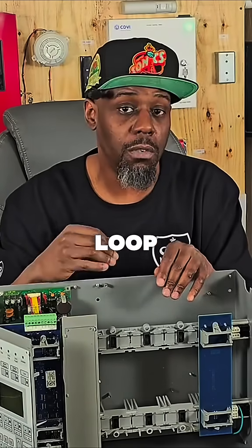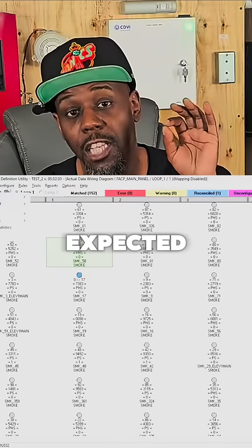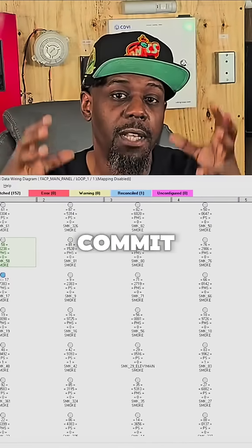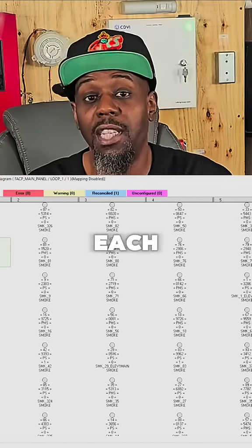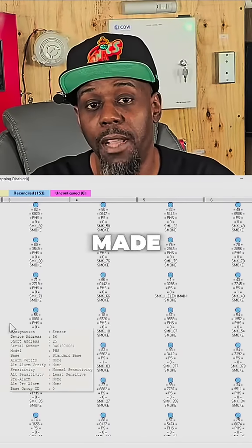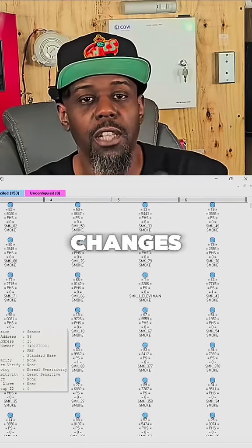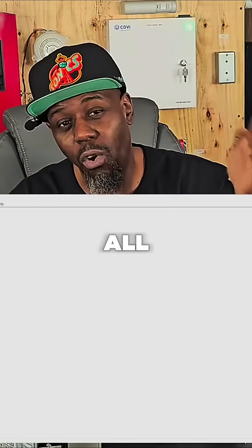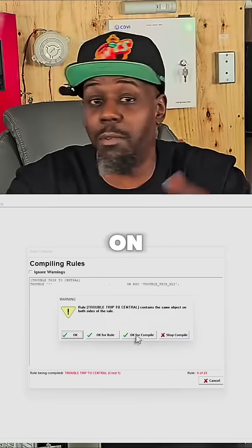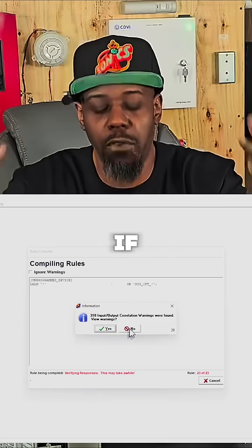What you want to do is, once you upload the loop, you want to commit the expected — that whole tree. Once you commit that whole tree, each icon would turn blue to let you know that you had made some changes. Then you go and compile. You compile all of your loop controller databases, or just the one you're working on, depending on how many map faults you have.